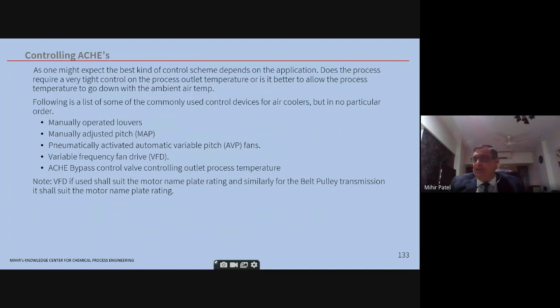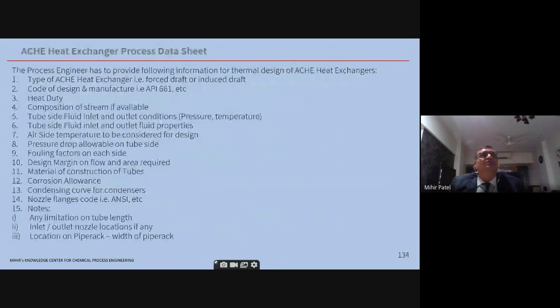Then the variable frequency fan drive (VFD). It's very popular nowadays for large fans, large ACHEs, to give 50% on VFDs, so that in winter times also you need not drastically subcool. You can save on power also. And the ACHE bypass controller. So these are the different methods used. Now, the process data sheet, again for ACHE. These are the things required for thermal design of ACHE.